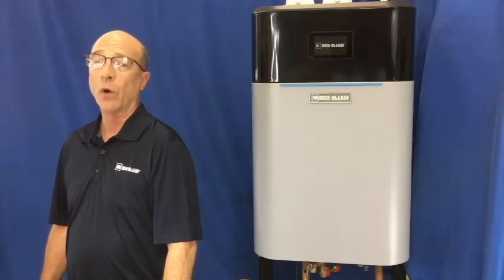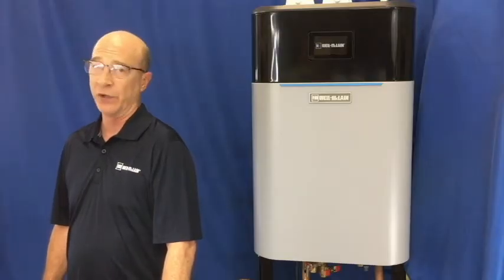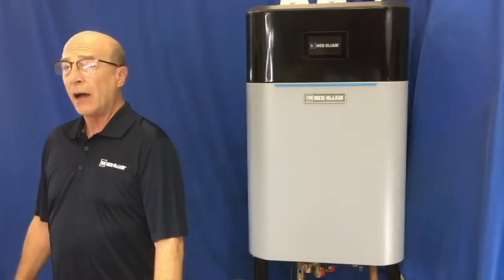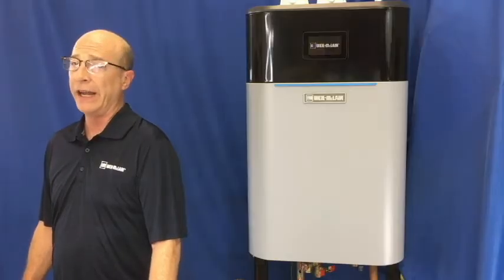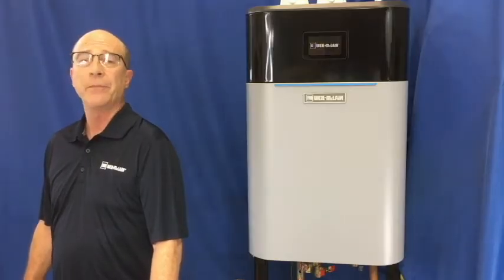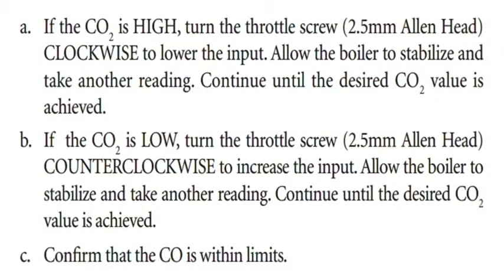The boiler will ramp up to its high fire setting. Now, observe the CO2 reading on the analyzer. If the CO2 is low, turn the throttle screw counter-clockwise. If it's high, go clockwise.